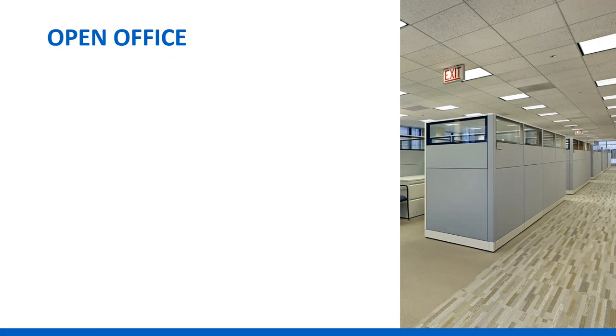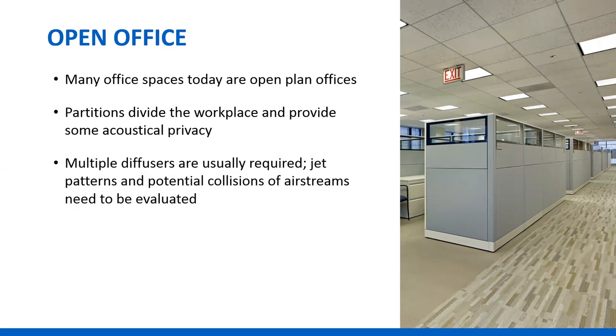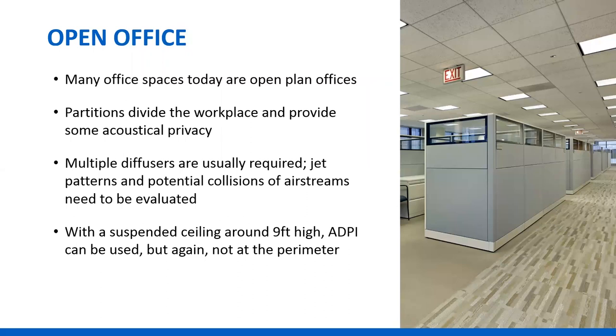Going back to our spaces: the open office. Most office spaces today have open plan offices. Partitions divide the workplace and provide some acoustical privacy. They also provide some interesting air distribution features, with multiple diffusers typically in repeated patterns. We can use ADPI if the ceiling is between 8 and 10 feet. We need to look at collisions of jets if you have higher or lower ceilings, and especially if you don't have a ceiling.